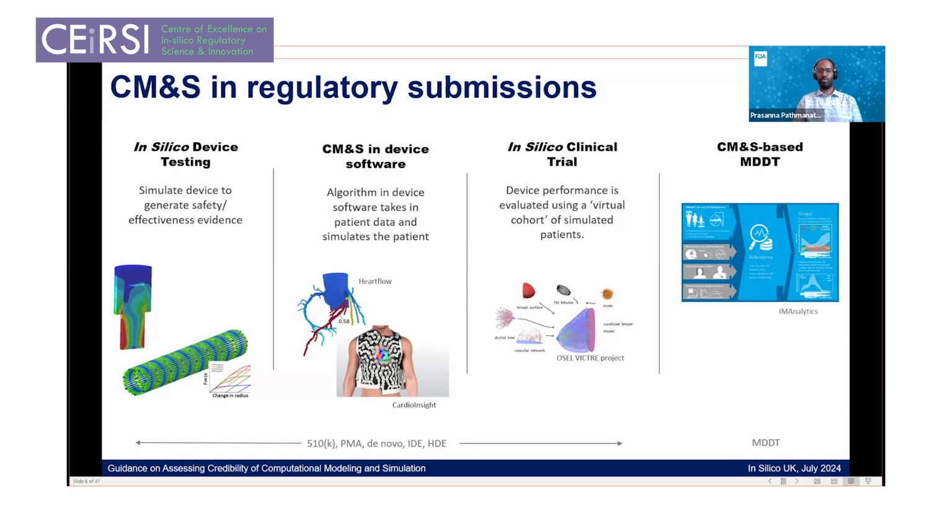And then FDA will qualify the MDDT, which means we look at how the MDDT is supposed to be used, what kind of information it provides, and the evidence supporting its reliability. And then if we qualify it, we say that we believe this can be used to evaluate devices, and we won't need to ask any questions about the methodology if it's used in the regulatory submission. We'll just look at the results. And obviously a model could be submitted as an MDDT.